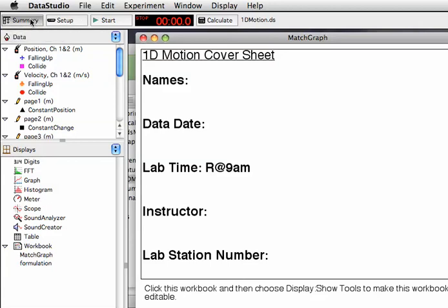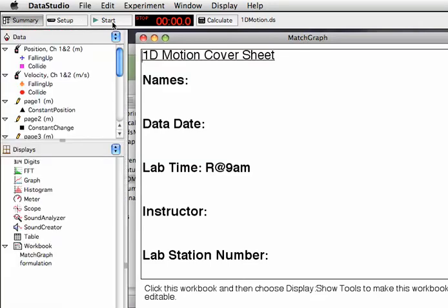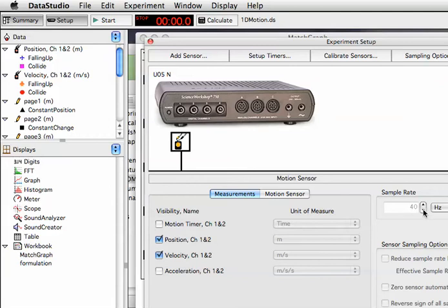And inside here is a setup button. There's also a summary and a start button, but we're going to use the setup button to begin with. The setup is going to allow us to calibrate the motion sensor. And over here you can see a sample rate in hertz, that's 20 samples every second. You can go all the way up to 50 samples every second with the motion sensor.